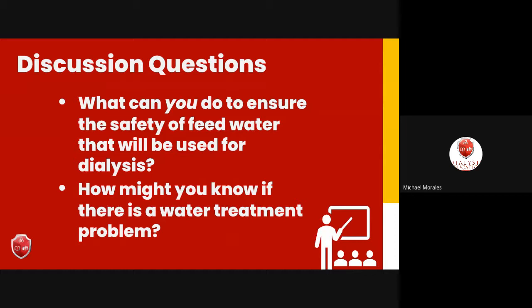If all patients have the same problem, we ask: what else do they all have in common? The same tech? The same machine? The same water? One water treatment system supplies product water to all machines in the facility — potentially 10, 12, 20, 24, or more patients running simultaneously.